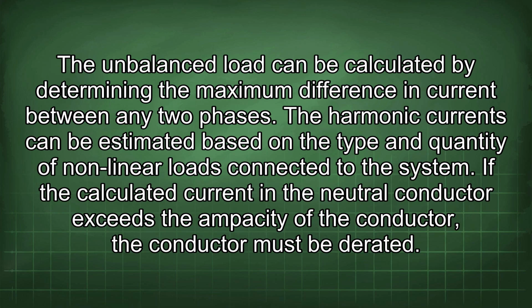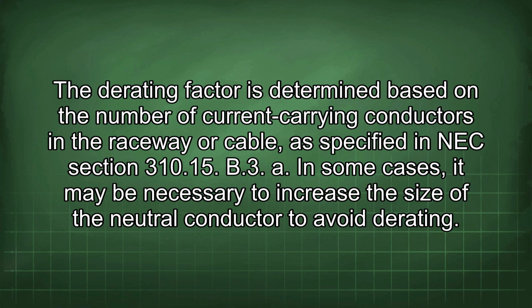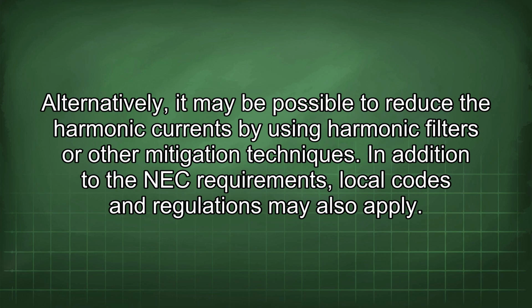The unbalanced load can be calculated by determining the maximum difference in current between any two phases. The harmonic currents can be estimated based on the type and quantity of nonlinear loads connected to the system. If the calculated current in the neutral conductor exceeds the ampacity of the conductor, it must be derated. The derating factor is determined based on the number of current-carrying conductors in the raceway or cable, as specified in NEC section 310.15(B)(3). In some cases, it may be necessary to increase the size of the neutral conductor to avoid derating. Alternatively, it may be possible to reduce the harmonic currents by using harmonic filters or other mitigation techniques.